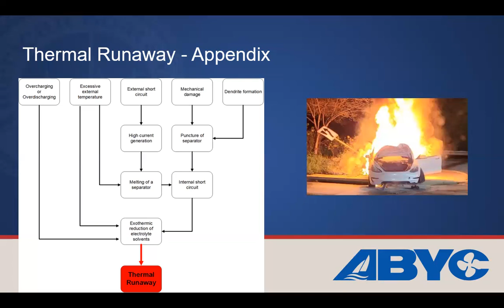Do they have any alarms that would say they're reaching thermal runaway? So usually, as long as you take whatever the outside influence is that's causing that problem away, you're not going to get there. Some of the BMSs can provide notice, depending on the application and installation. The standard does not require a warning, but some systems, like a bigger system with an external BMS, can provide that information. The typical drop-in solutions aren't going to provide that.